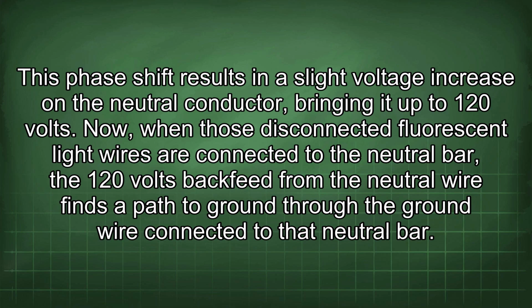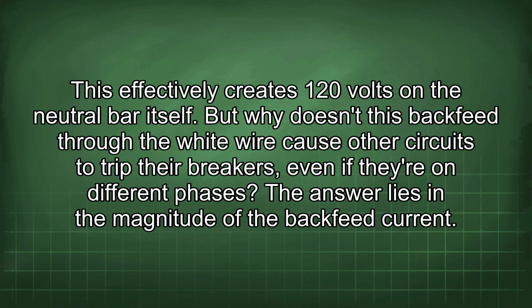Now, when those disconnected fluorescent light wires are connected to the neutral bar, the 120 volts backfeed from the neutral wire finds a path to ground through the ground wire connected to that neutral bar. This effectively creates 120 volts on the neutral bar itself.